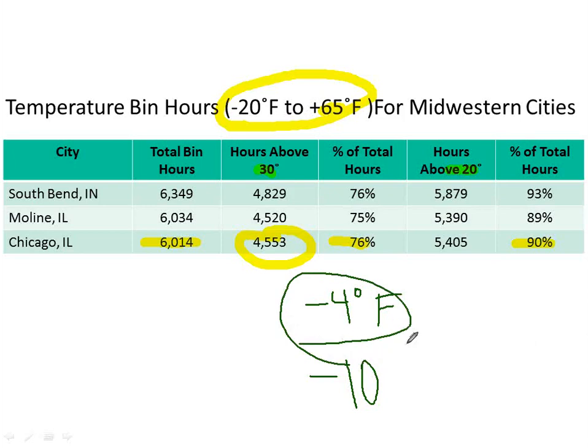But let's just say, for sake of argument, -4 degrees outside, but 20 degrees and above is most of my hours. So if I give you a regular furnace for, let's say, 80,000 BTUs, like our previous example, designed for a -4 degree day outside, it's great. On the -4 degree day, he's rocking and rolling. He's got all stages fired. He's happy and running. But anytime it's warmer than -4 degrees, he doesn't need all of the stages' capacity. And if you only got a one-stage unit or maybe a two-stage unit, it's a little bit harder to keep up with that.